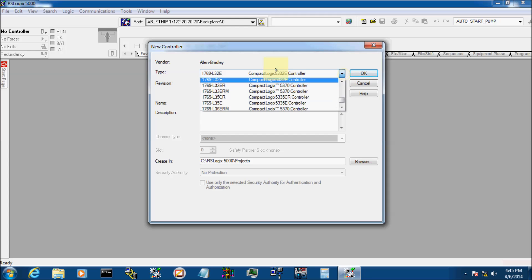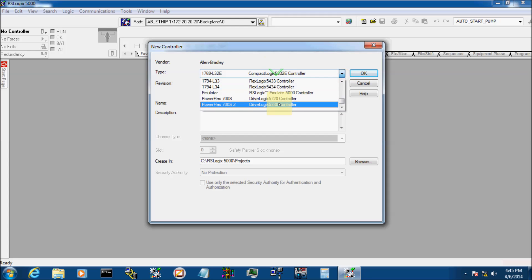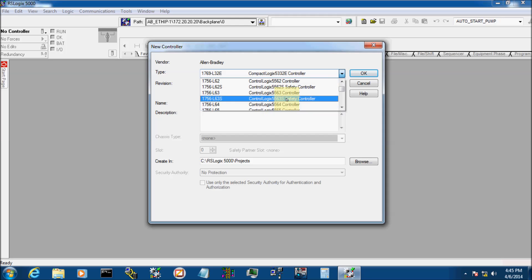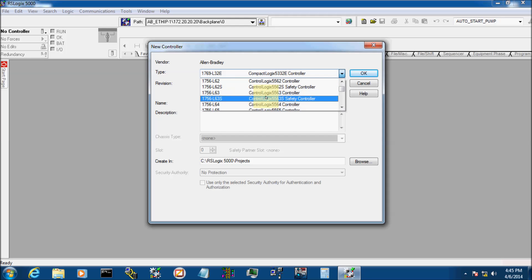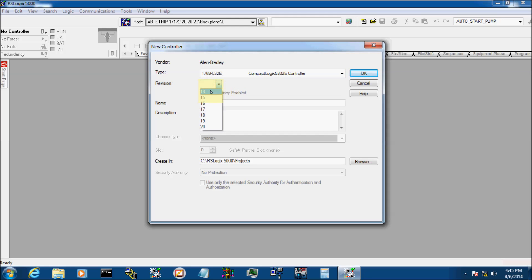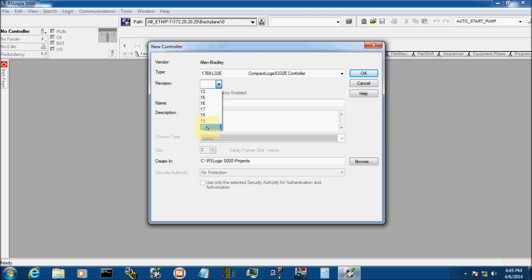Click up here, you can pick between any of the ControlLogix family of processors. The processor I'm actually using today is a 1769L32E Compact Logic. Under Revision, this is where you have all the revisions of the firmware available with your version of RSLogix 5000. I suggest to go at the highest revision number. Each major revision has a little tweak here and there, so it never hurts to go high.